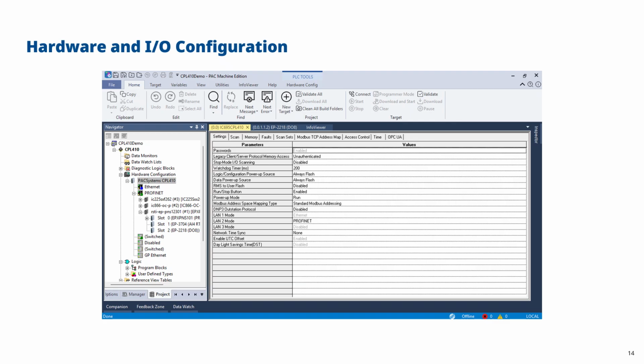Under the faults tab, you can select fault categories. Fault categories would either be informational only, in which case it's logged into the fault tables but the CPU carries on running, or you can have fatal faults that will stop the CPU from executing. So for example, if you had a backplane fault or a memory parity fault, you can choose for that to be a fatal error that will stop the PLC.